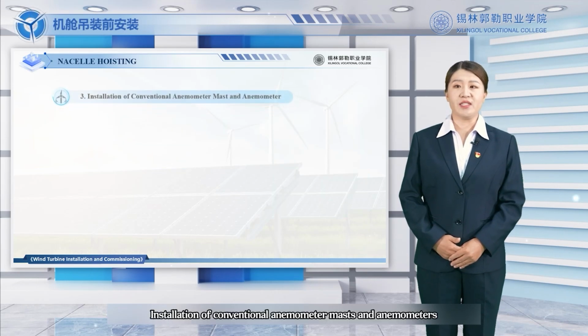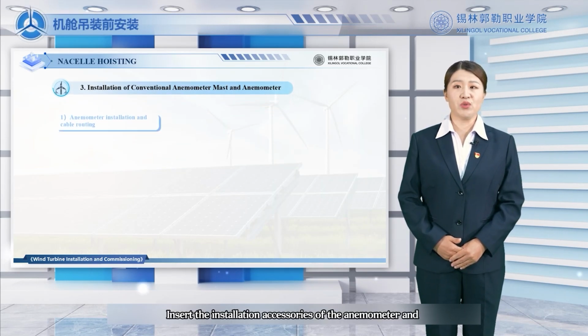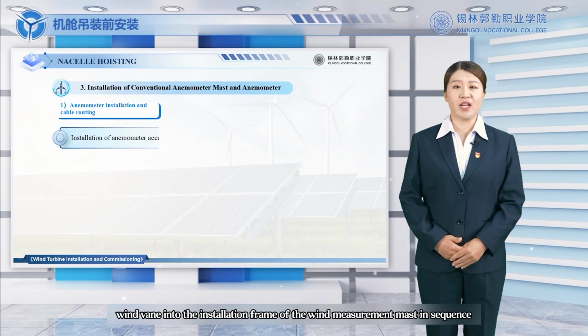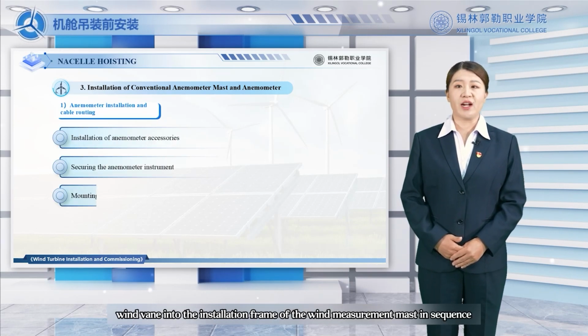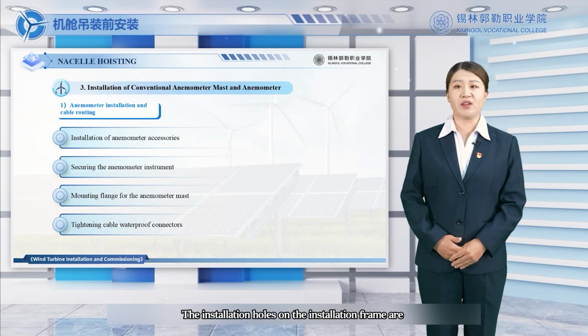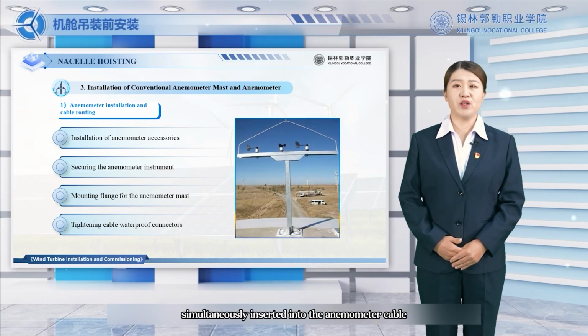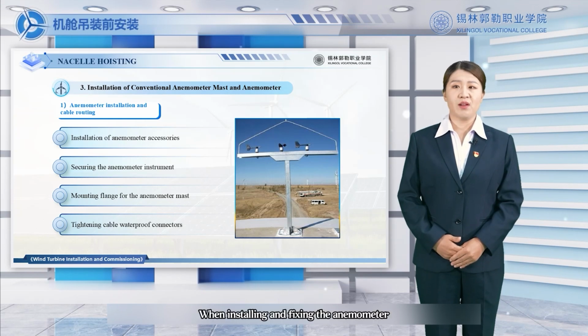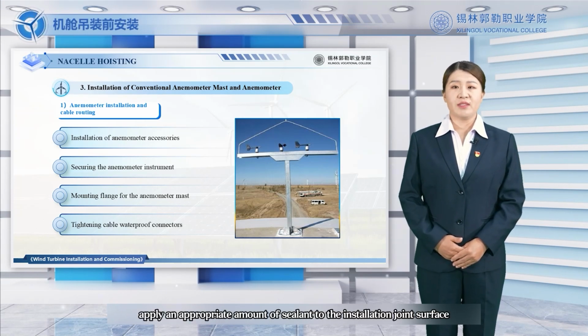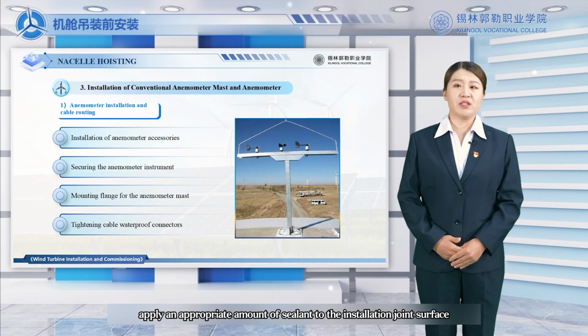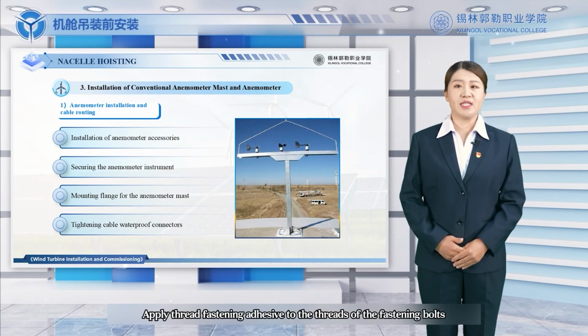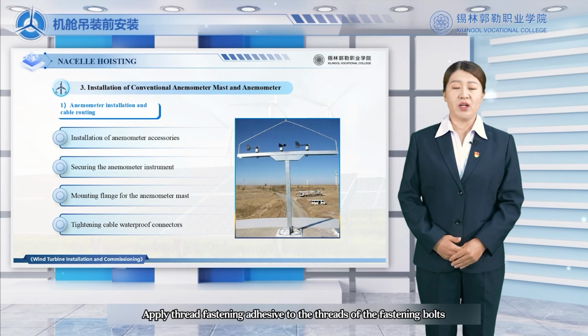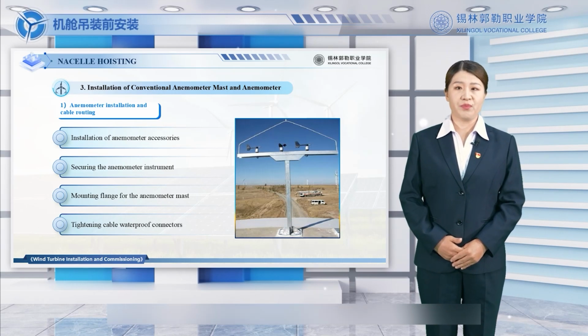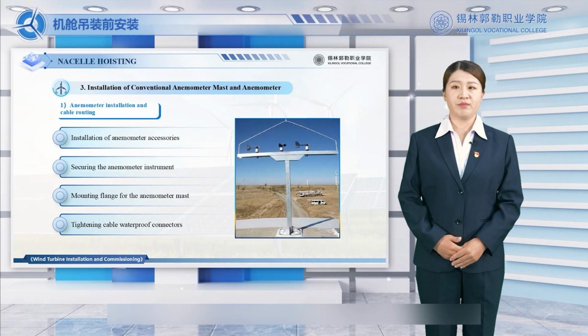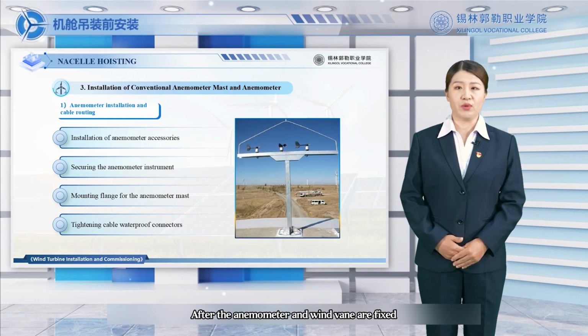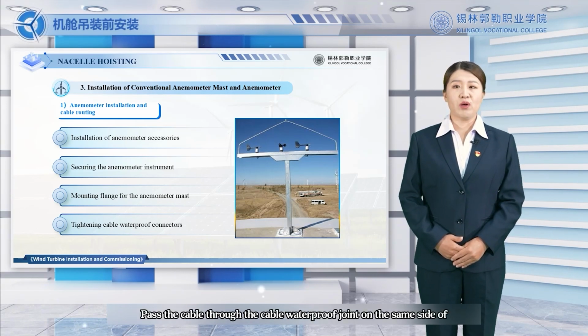Installation of conventional anemometer masts and anemometers. Insert the installation accessories of the anemometer and wind vane into the installation frame of the wind measurement mast in sequence. The anemometer cable is simultaneously passed through the installation holes on the installation frame. When installing and fixing the anemometer, apply an appropriate amount of sealant to the installation joint surface. Apply thread fastening adhesive to the threads of the fastening bolts. Finally, tighten the bolts.